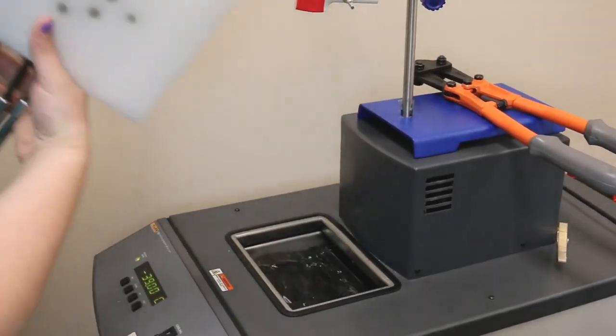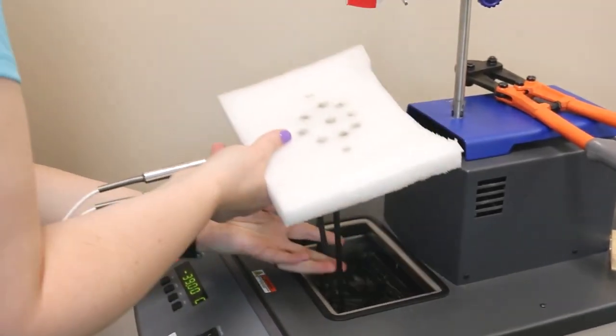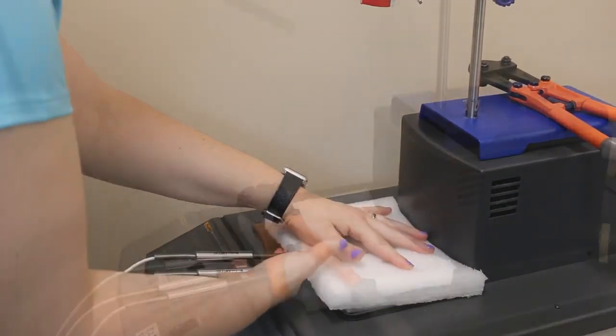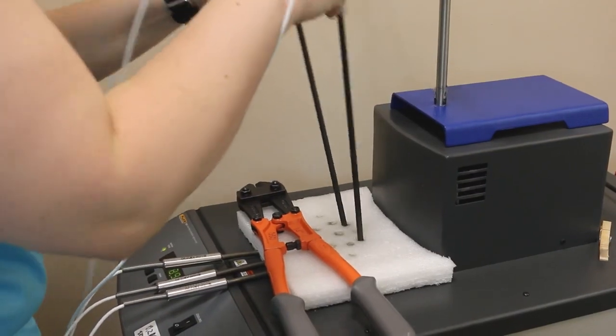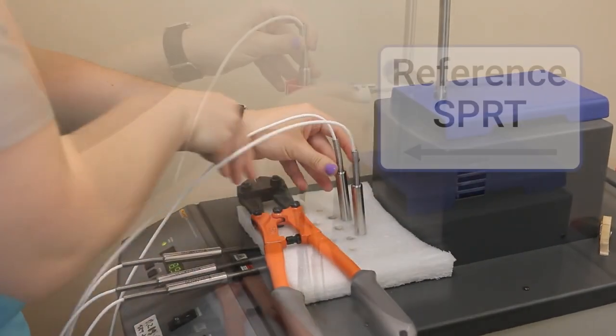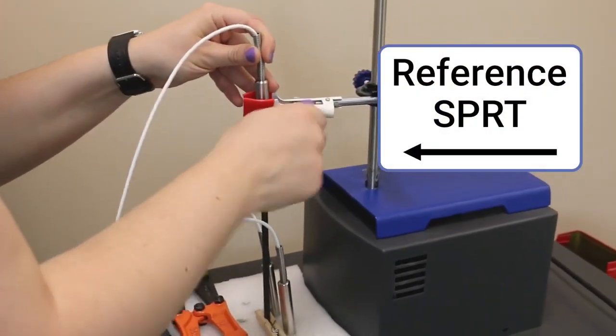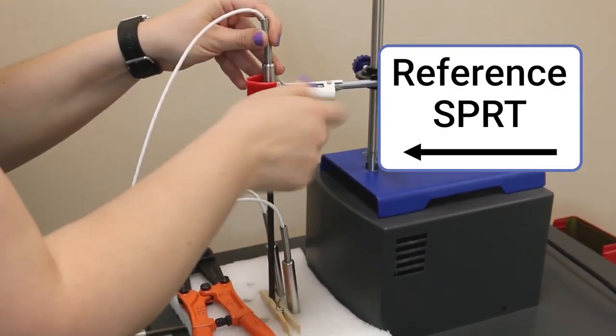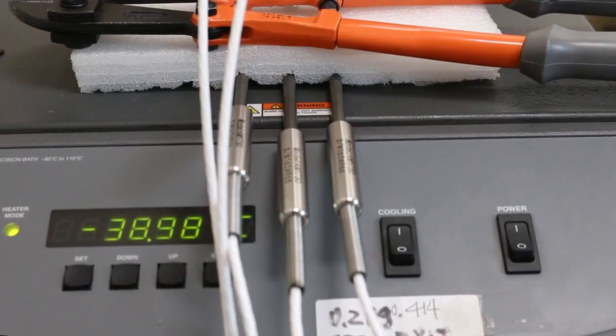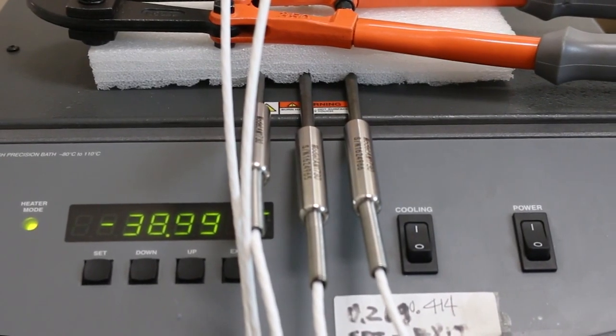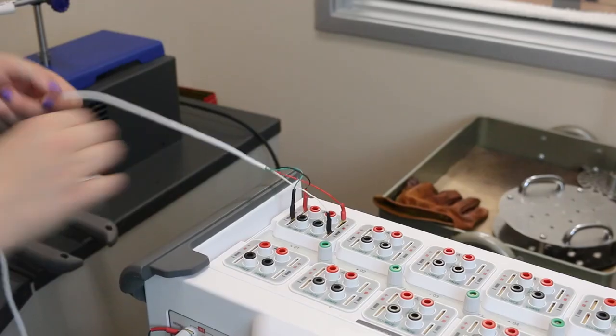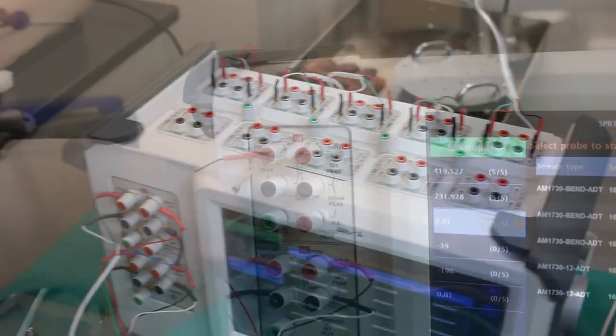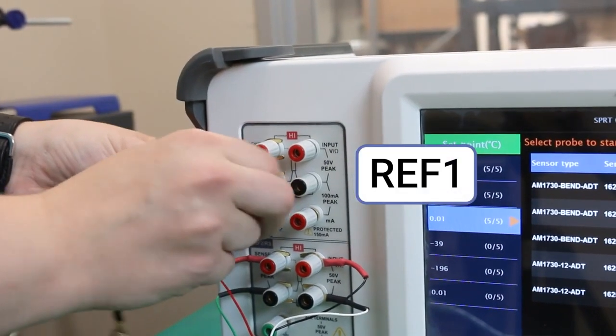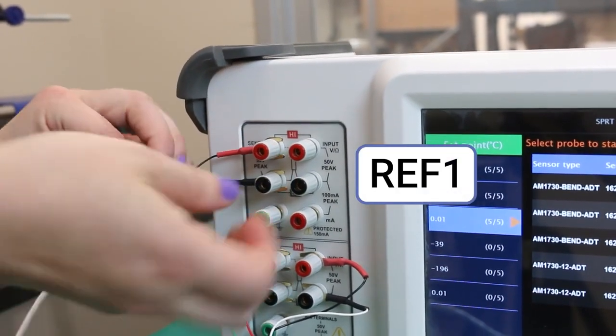Comparison calibration points can be used in place of fixed points in order to complete a calibration without having the equipment to actualize fixed points. To replace the intrinsic reference, a reference SPRT must be used throughout the test, which will be compared against the DUT probe readings. Since the -39 degree bath is large enough to fit all of the probes at once, we can connect all 5 of them to the ports on the top of the 286. We will also connect the reference SPRT to the REF1 channel on the front of the 286.